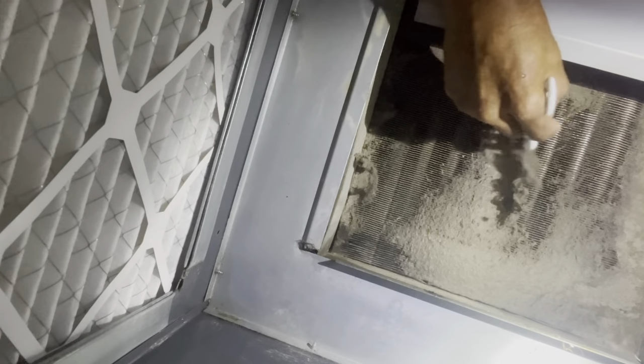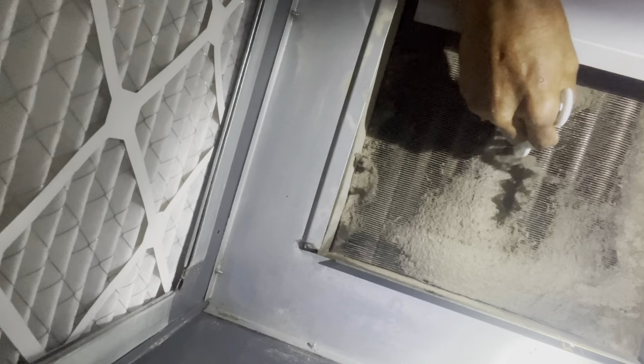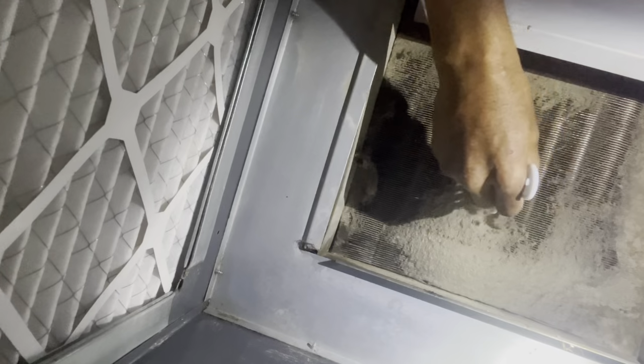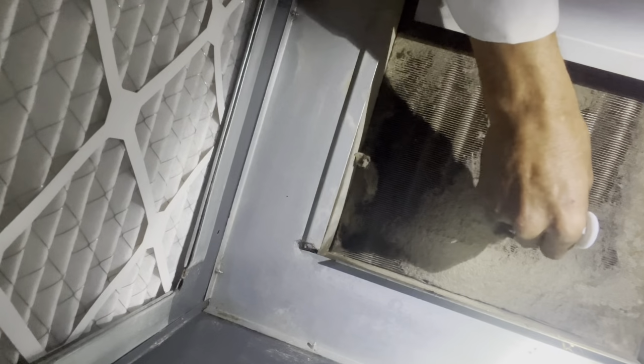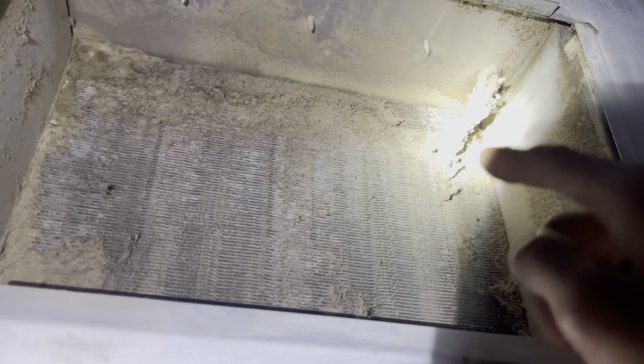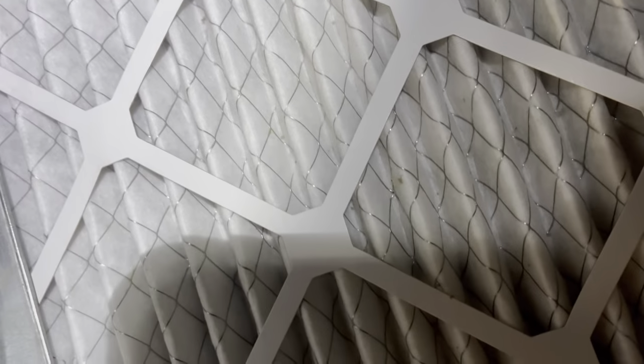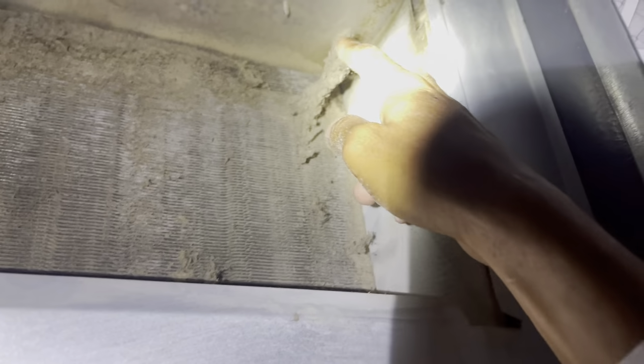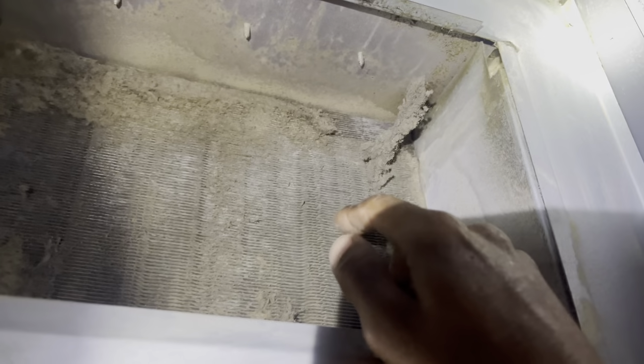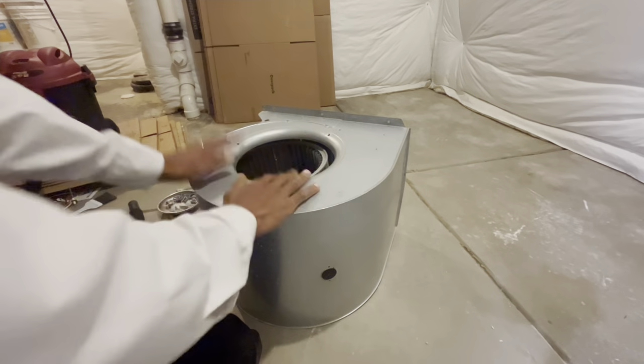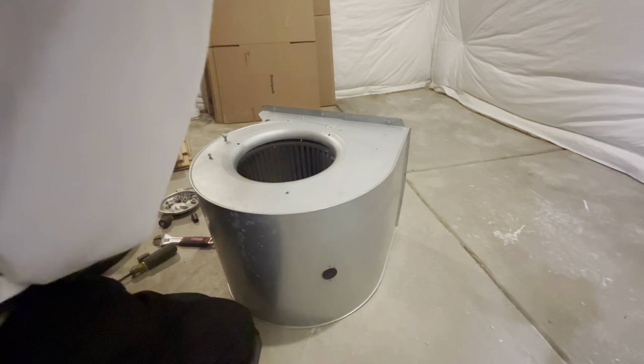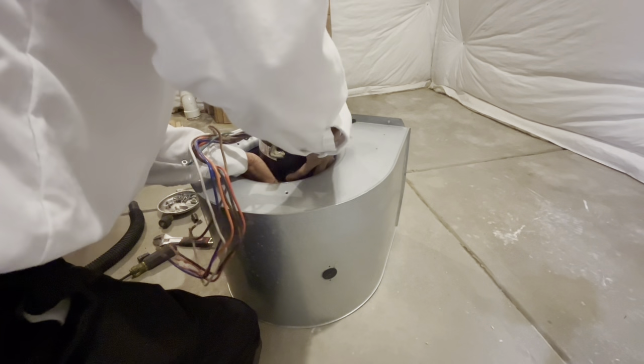So the secondary heat exchanger is kind of like a small radiator, in the sense that you can see the fins on the bottom. You need to make sure that you're very careful with the fins of it. That's why I'm taking this condensate brush and being very easy and gentle on them, not bending any of the fins. I do not want to restrict airflow going into the system. I want to make sure that everything stays in factory specifications as much as possible. So that's why I take my time with that brush and get as much of the buildup off as possible. In a sense, I guess I could have used that shop vac, but I find the brush works well. And sometimes I get tired, so I skip parts.